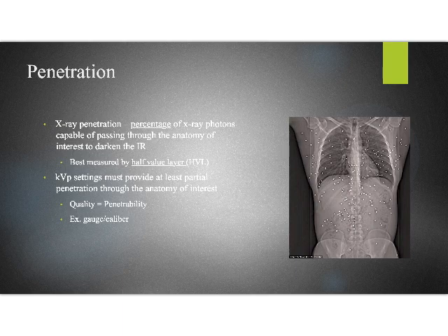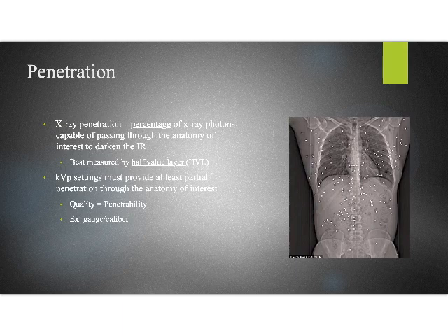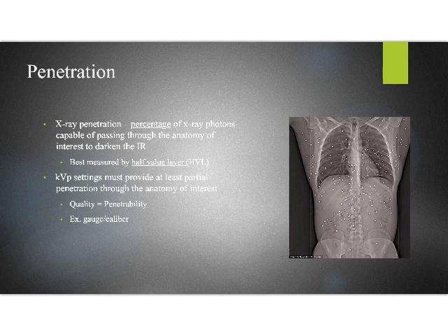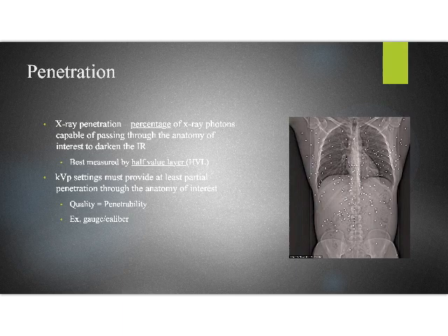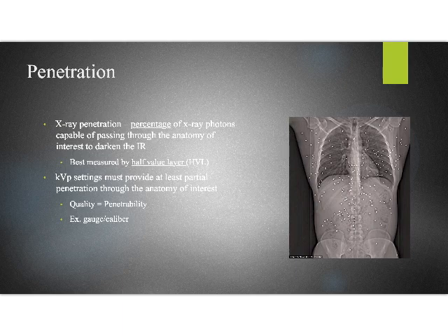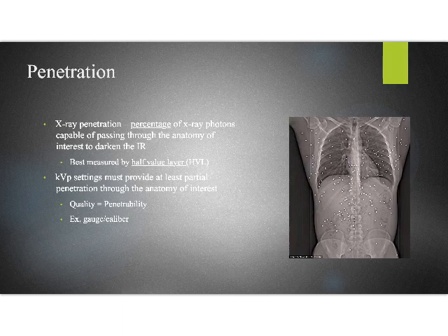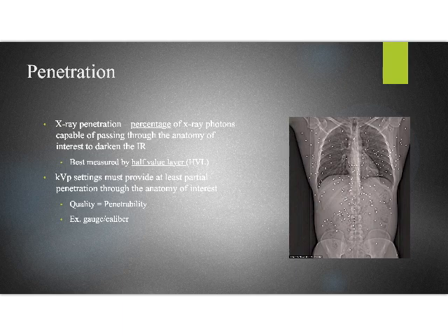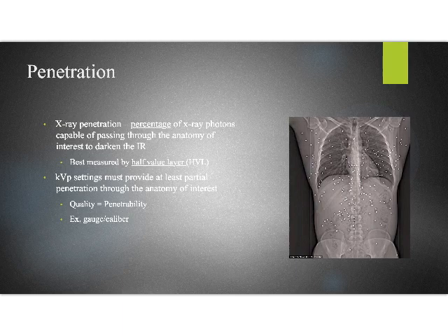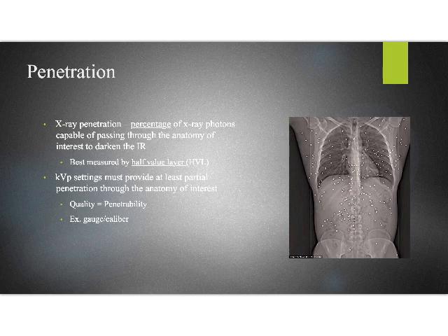So the same thing happens with the x-ray. If we think about KVP controlling the penetrability of the x-ray beam, what it's doing is controlling the percentage of x-ray photons that are capable of passing through the patient's body and darkening the image receptor. It's controlling the power that we're placing inside the x-ray photons to pass through matter. So if this man had been shot with a more high-powered shotgun, more of this buckshot would have passed through his body. Same as what's happening when we control KVP in the x-ray circuit. The best measure of this penetrability power is half value layer.